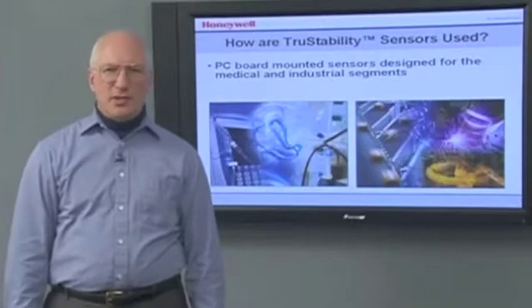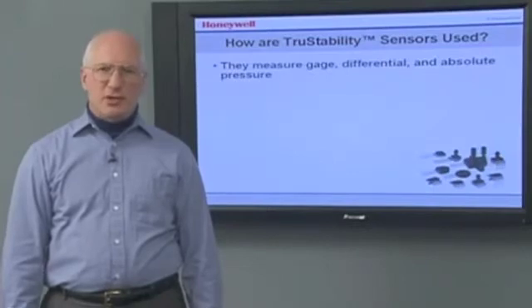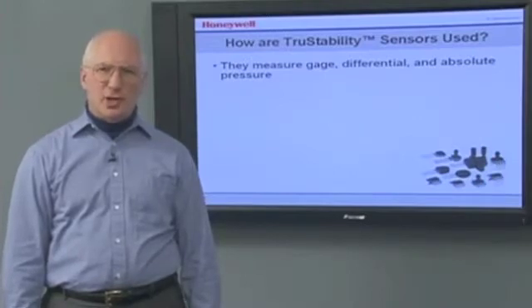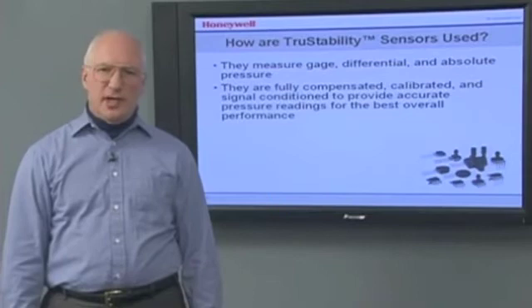How are TruStability Sensors used? TruStability Sensors are PC board-mounted sensors designed for the medical and industrial segments. These sensors measure gauge, differential, and absolute pressure to give you information about a key parameter for your application or to help you control how your application operates. They are fully compensated, calibrated, and signal-conditioned to provide accurate pressure readings for the best overall performance.